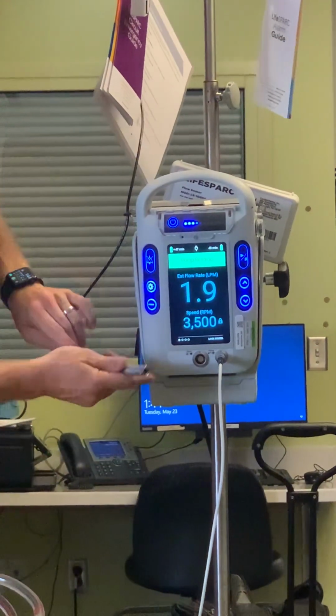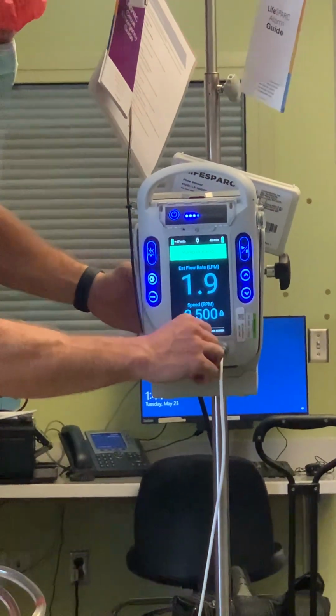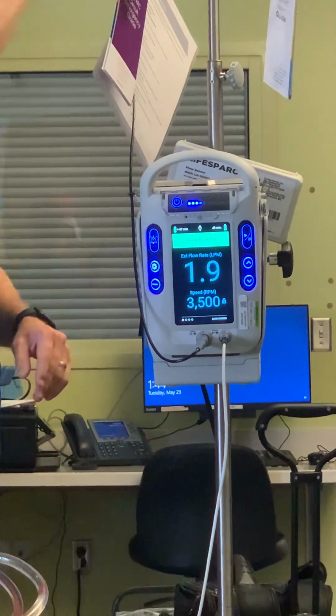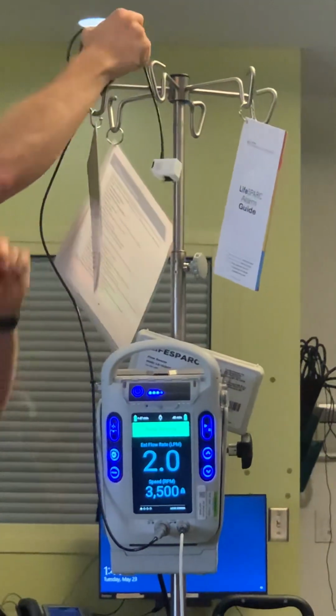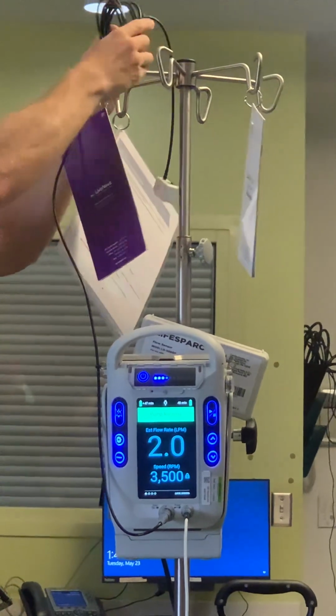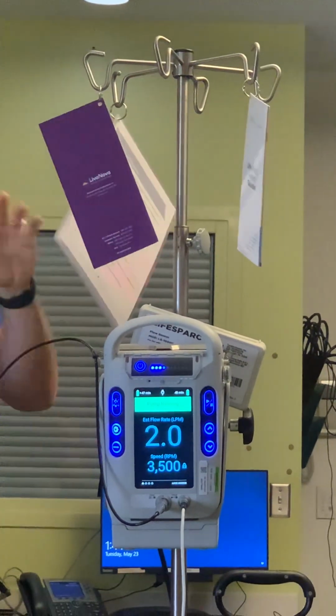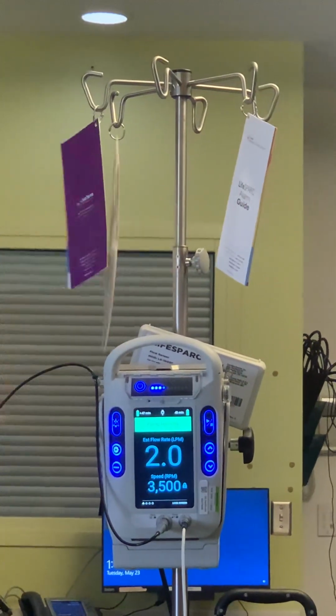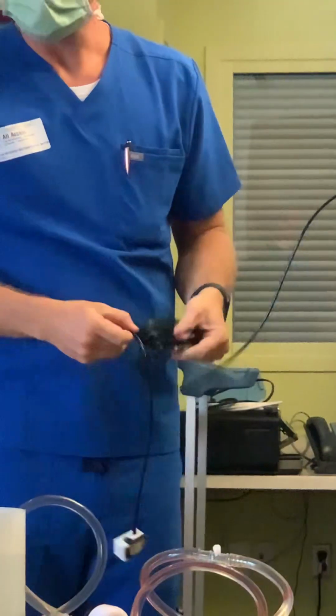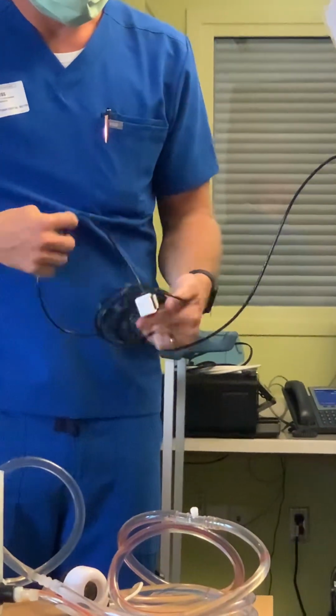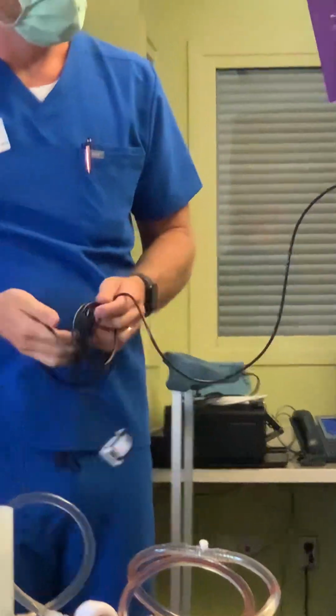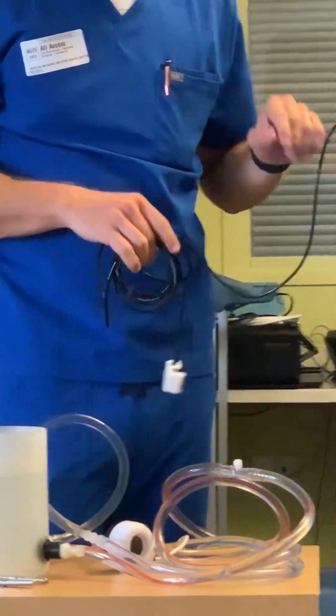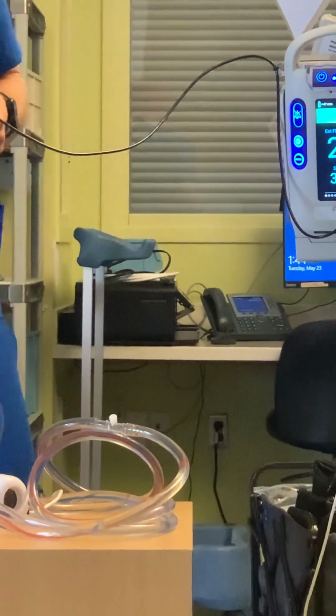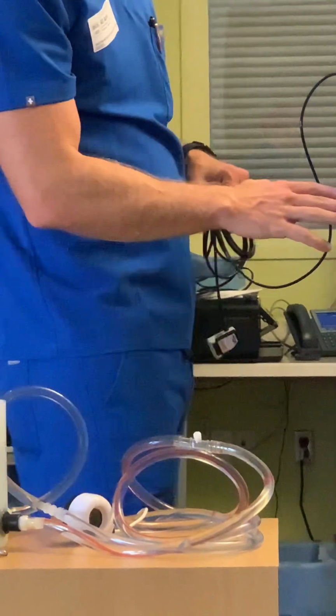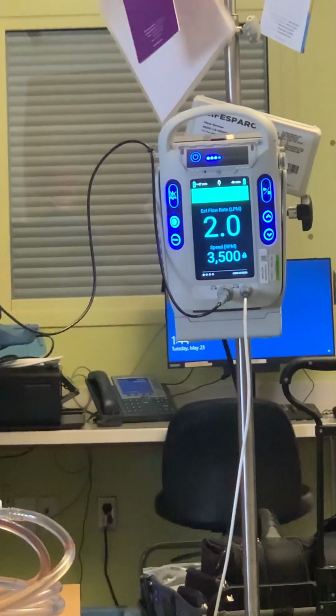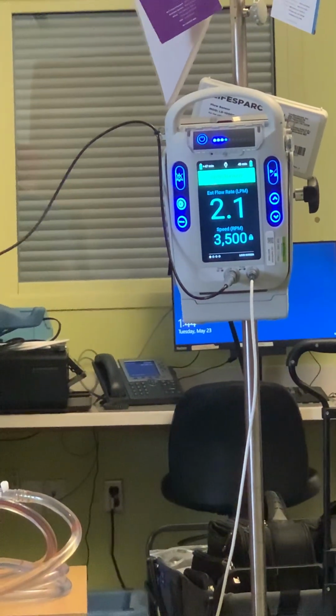And then once the patient's on support, we can hook up our flow probe, which is a non-sterile part. You can sterilize it, however, then you have to make sure that it stays with the circuit. But it's all physician, it's all site dependent on how they want to do it. The flow probe needs to be on before they go to make any changes, because this can be plus or minus 1 to 1.5 liters of flow.